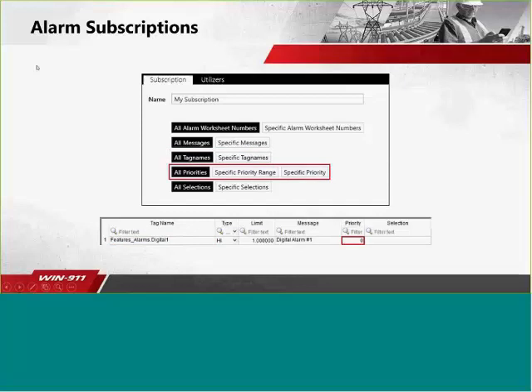So in Web Studio, let's say 0 is your high priority. I only care about high priority alarms. So I create a subscription that says, give me all the alarms that are priority 0. Then if an alarm occurs and is that priority, it comes into Win911. Maybe this subscription, you set it to a call-out list that notifies people immediately. And you have another subscription that brings in lower priority alarms and sends to a call-out list that has a built-in delay of maybe 10 or 15 minutes to give the alarm some time to normalize before actually calling anyone.